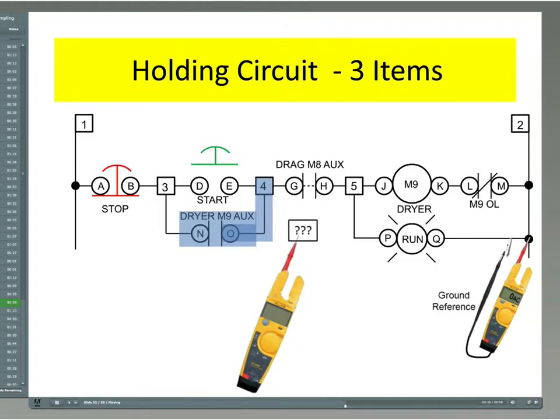How could this problem be isolated using a voltmeter? The voltage at terminal O can be supplied from 2 different directions, from the start switch and from the aux contact. When isolating the voltage, one of the paths has to be eliminated. A process of elimination is to disconnect a wire and feedback path from the start switch to the M9 aux contact.